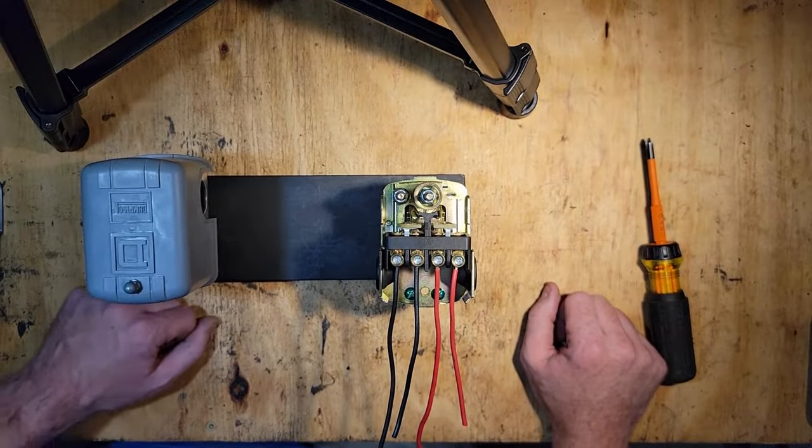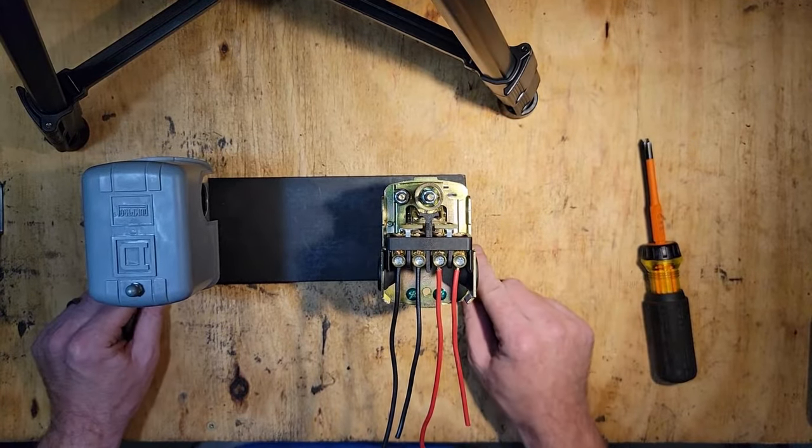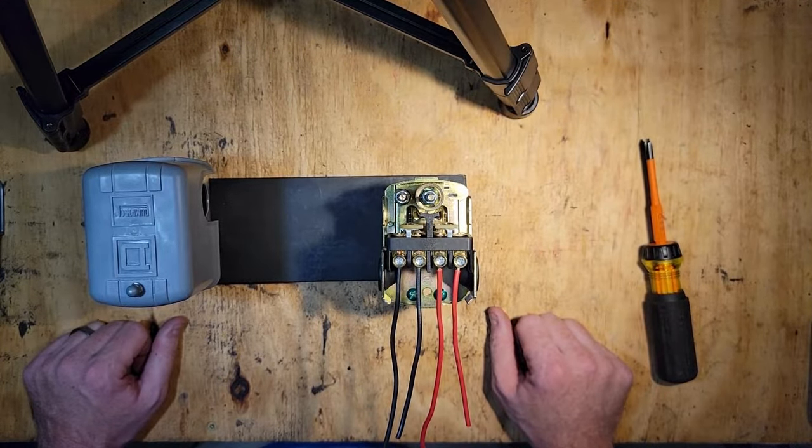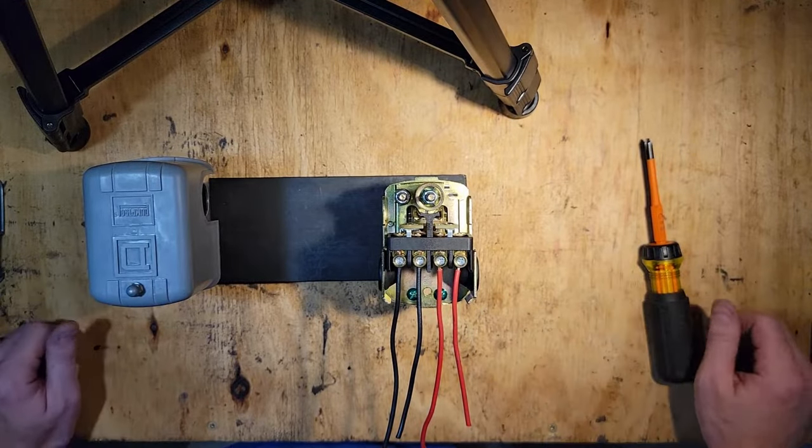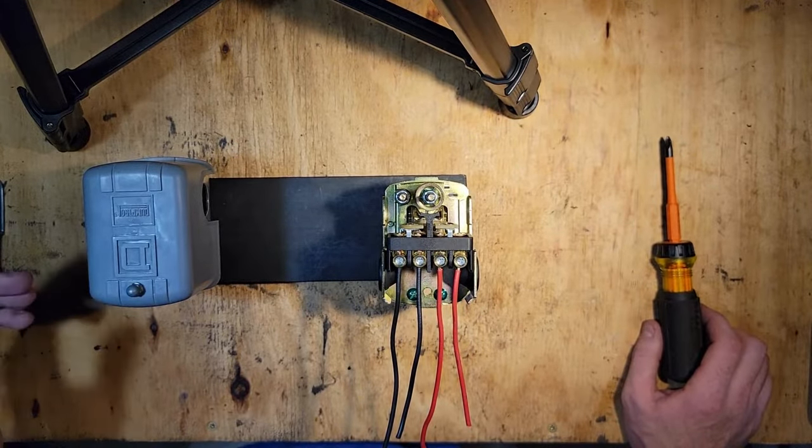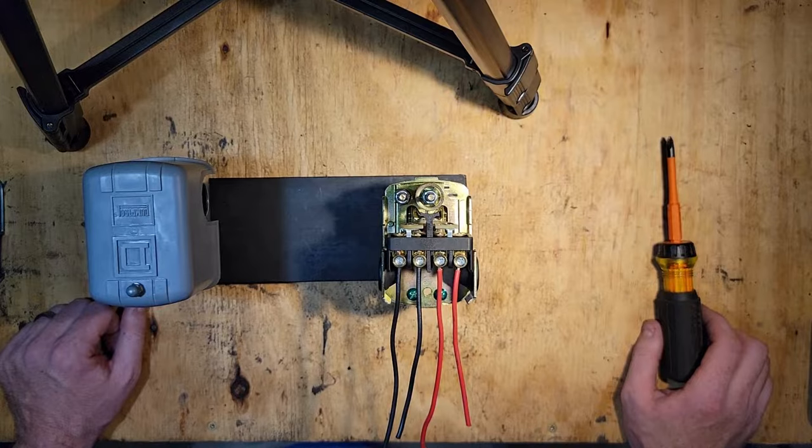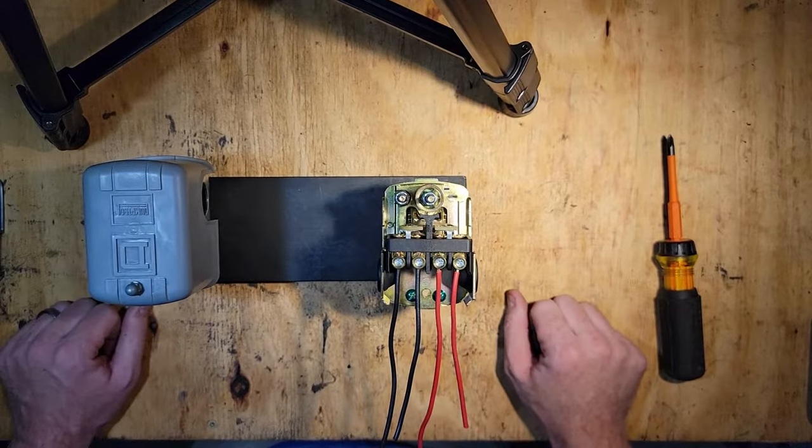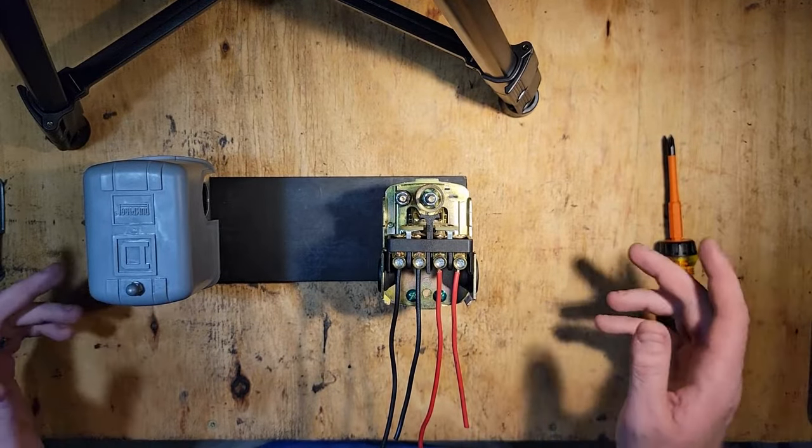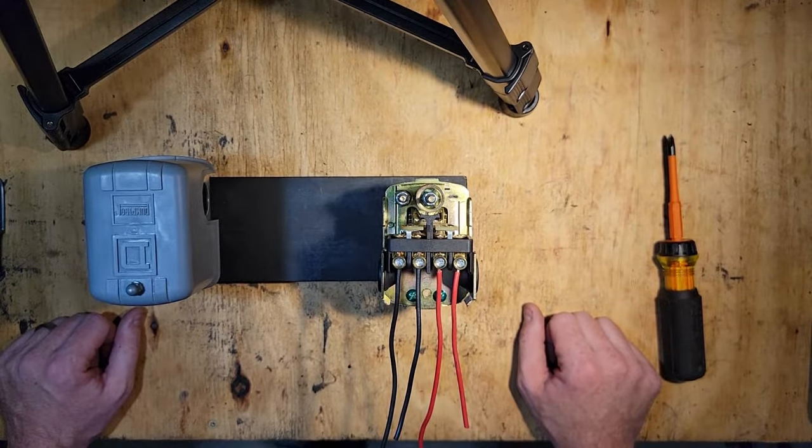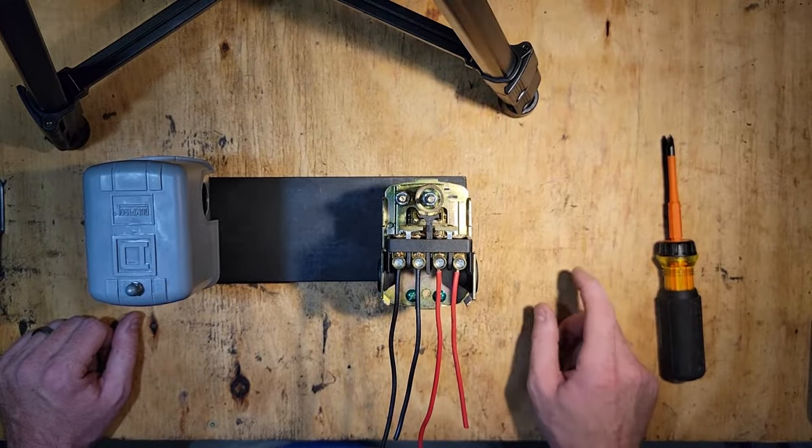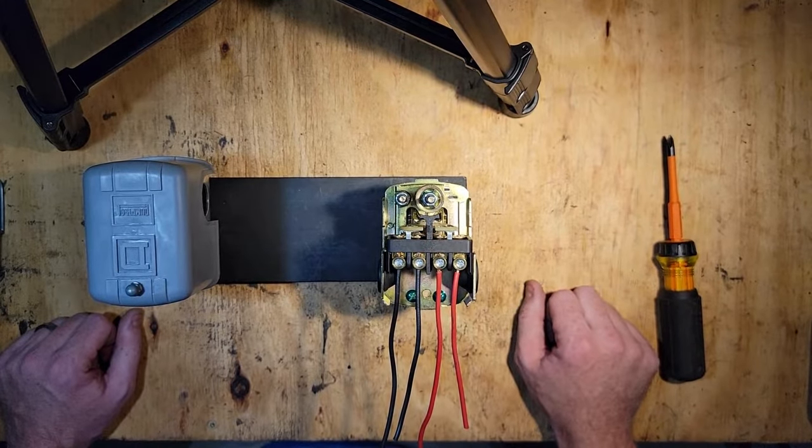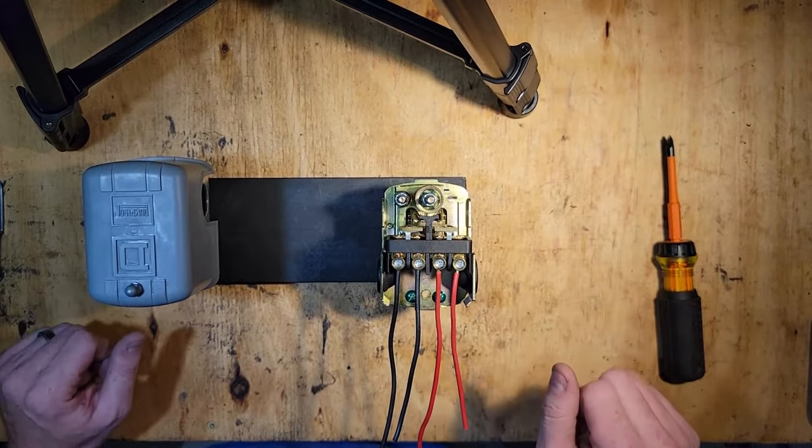Your smaller control boxes, your half horsepower, three-quarter horsepower, one horsepower, are pretty much usually standard boxes and don't have the option. The middle ones, your horse and a half and two horsepower boxes, can be either or. But it's pretty simple to check. You can just take the cover off your box and you should have an SW terminal on that main strip if yours is a deluxe box.